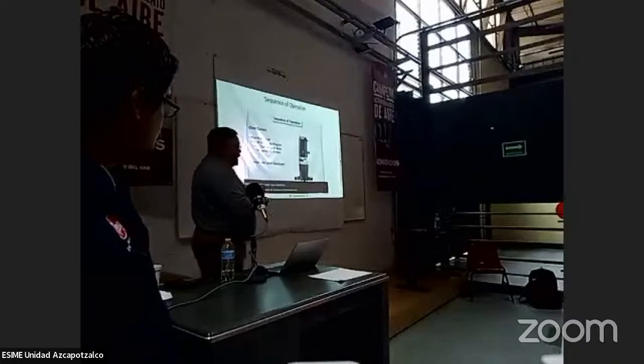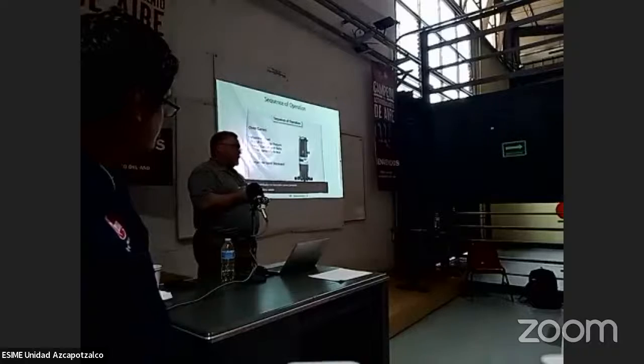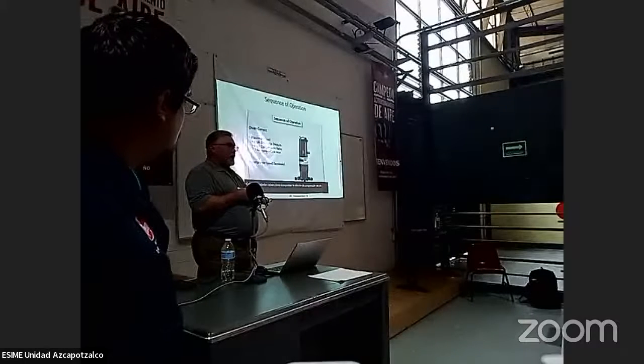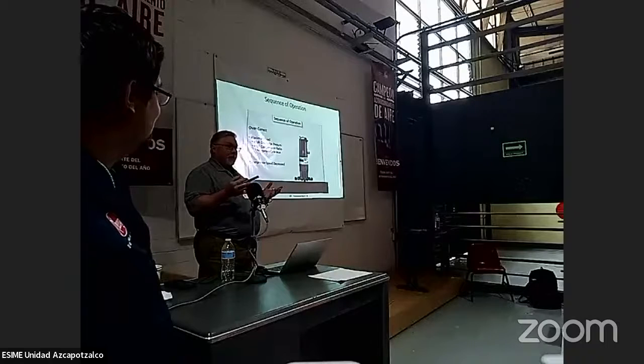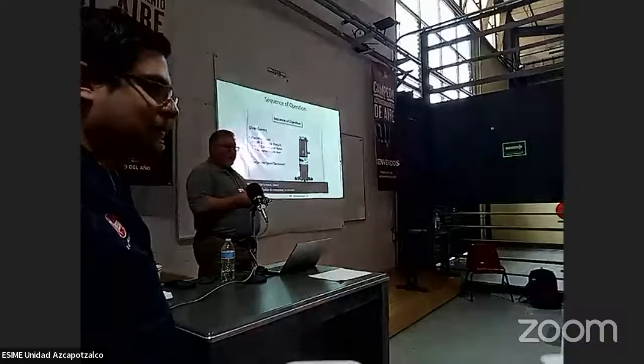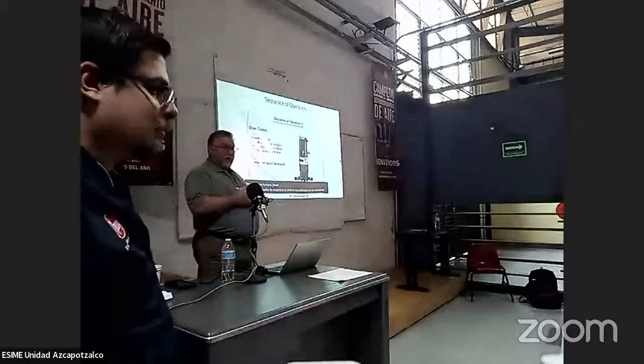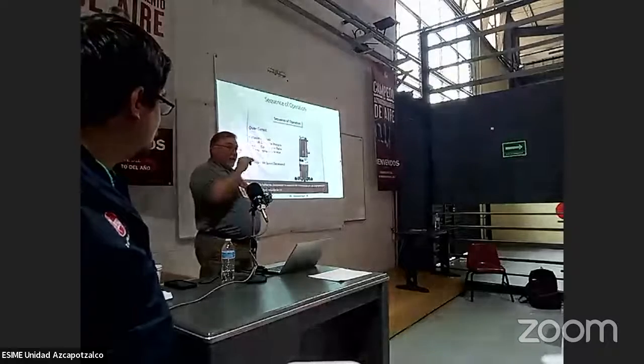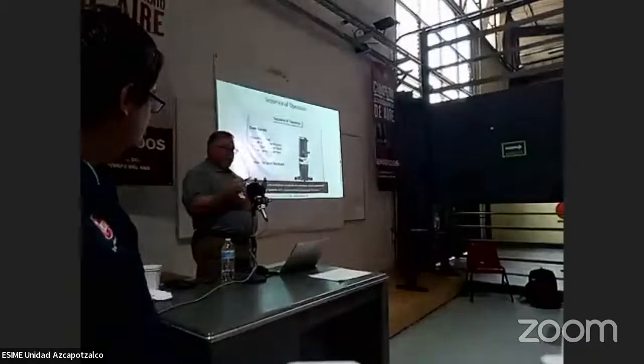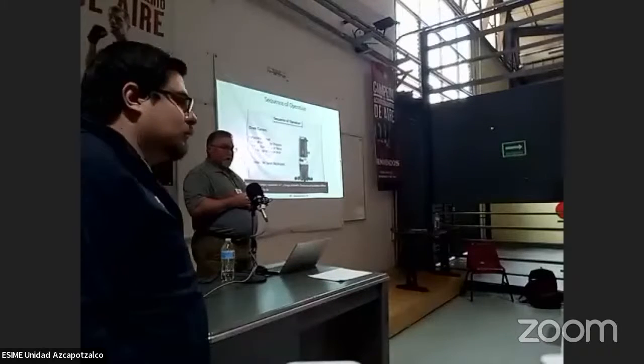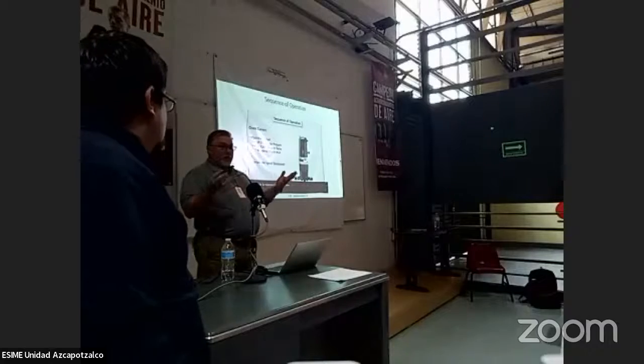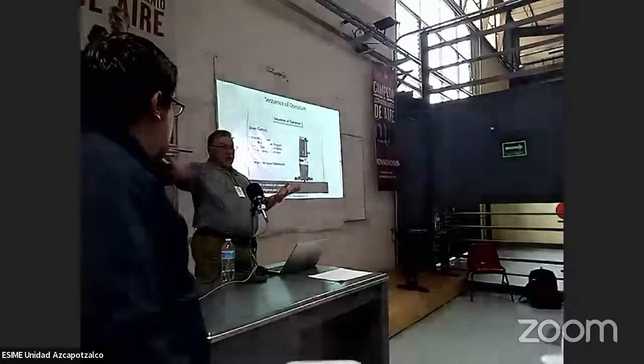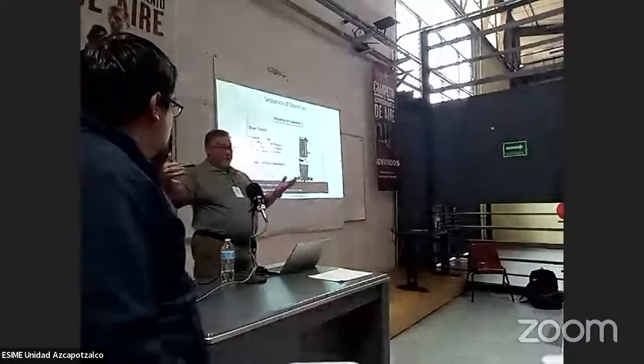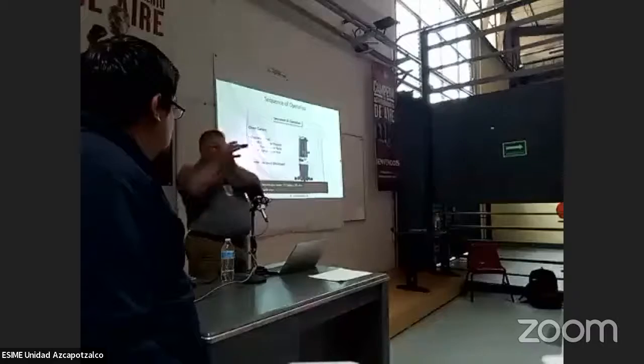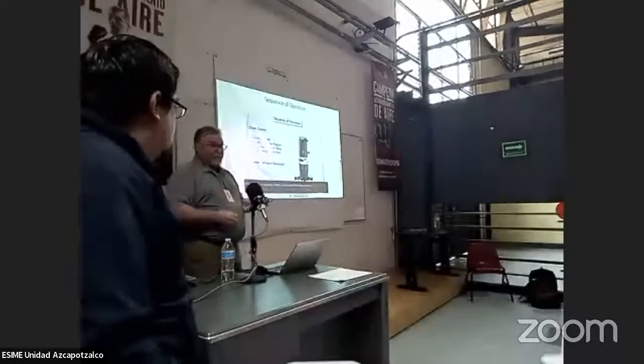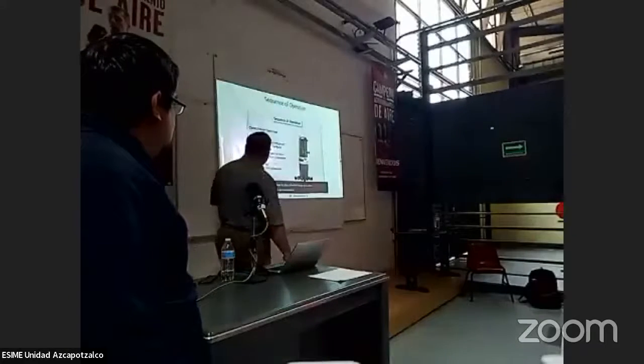Okay. How many of you know how to check the compression ratio of the compressor? Stop raising your hand, David. Nobody? You ever heard of checking the compression ratio of a compressor? Just checking low, high, fluctuating discharge. Add 14.7, and then divide the low into the high. That gives you your compression ratio. Low divided into high. So let's say you have 125 low and 336 high, and you add 14.7 to each. Take the high and divide the low into the high, and that will give you the compression ratio. Okay, so see if it shows you. Sorry.